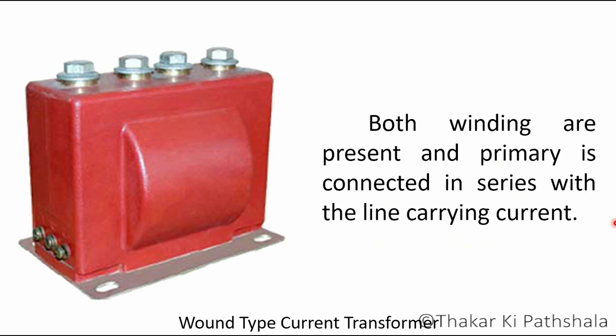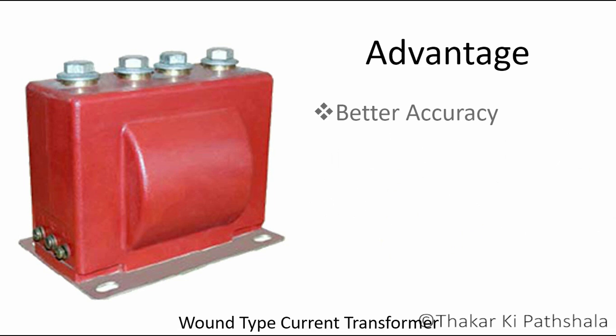Advantage of this type of CT is that designer can make unit with low current ratio, have better accuracy and burden capabilities. Wound type current transformer is the most effective way to achieve the desired performance, especially for the low current ratio requirement.